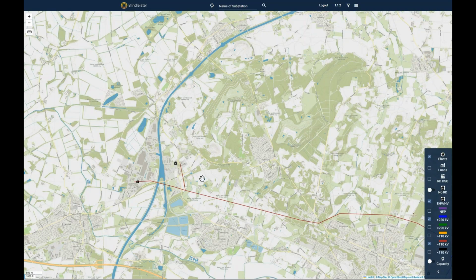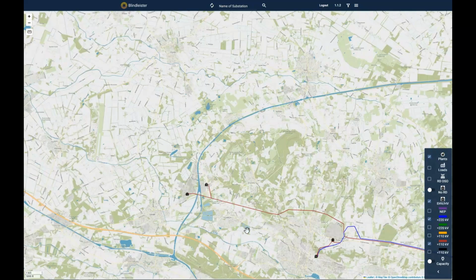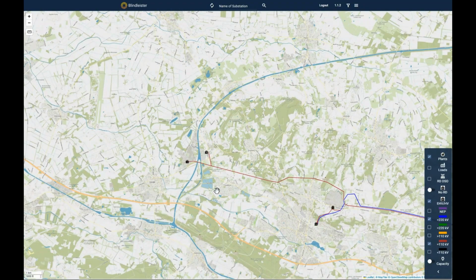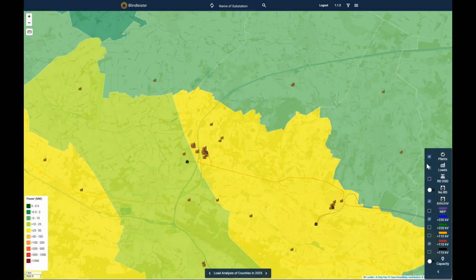But what's a good size now to request? We understand now the constraints, which are mainly coming through this line here. And they are not going away in the near future. If we have a look at the grid development plan, there is a line planned from here, 60 MVA are planned, but it doesn't really affect this area. We also look into the loads that are planned in the near future, but we see nothing new is planned here, so the load won't change much.